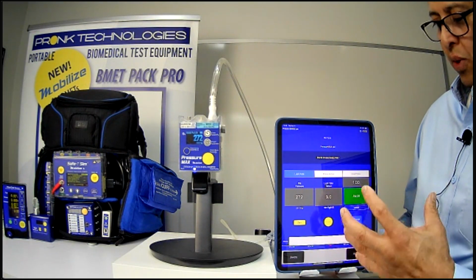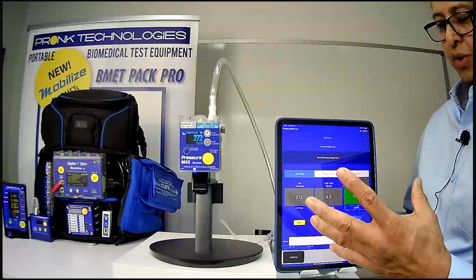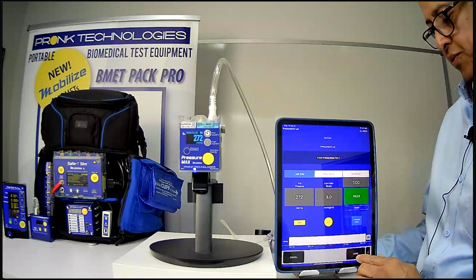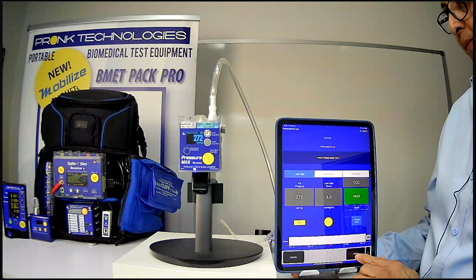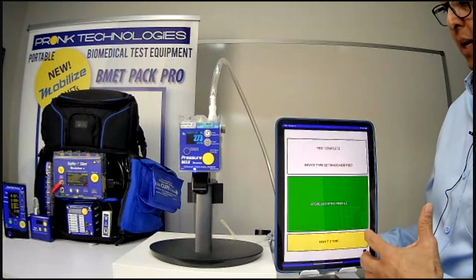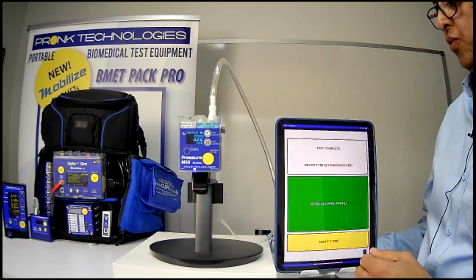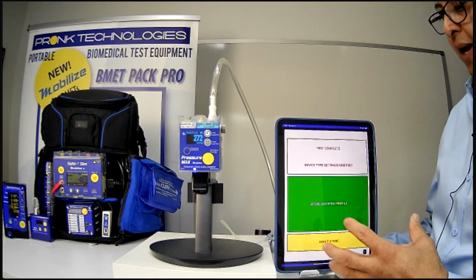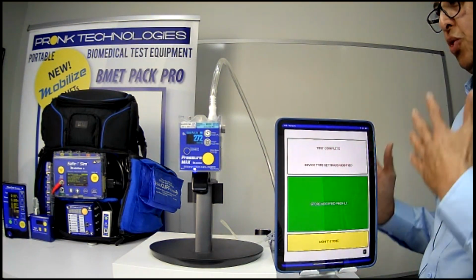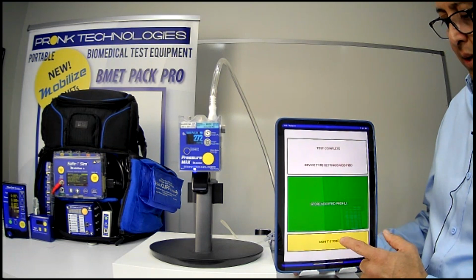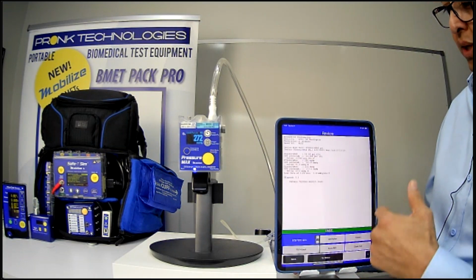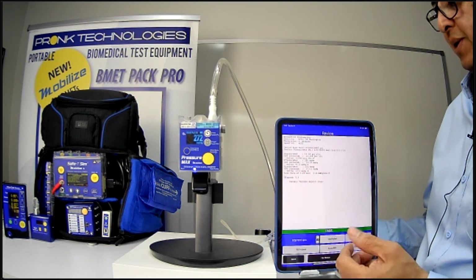It really is a great way to utilize the Pressure Max when you're testing medical devices and capture your results without having to write anything down. Once I'm done, it's giving me the option: do I want to save any setting changes that I made? You can do that and save it as a new test protocol if you'd like. I'm just going to go ahead and hit no, and it takes you to the report. We just did a basic test here.